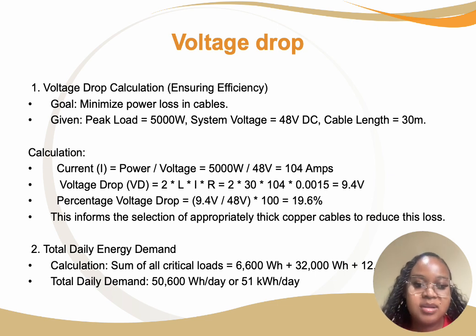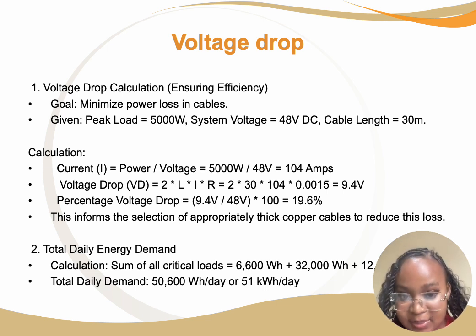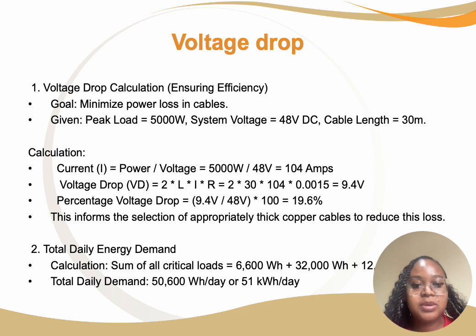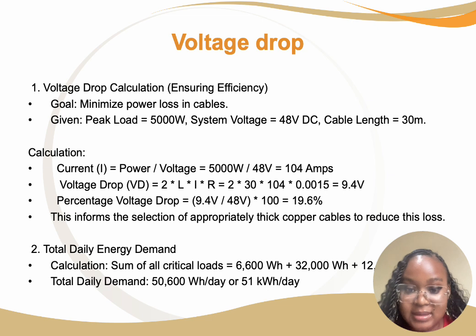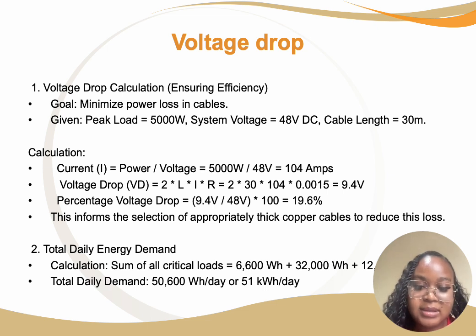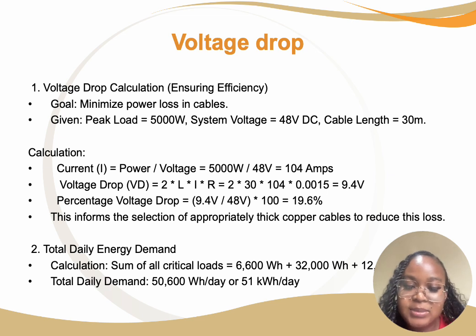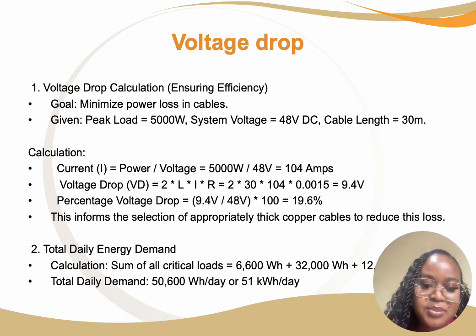Then we went and calculated our voltage drop. The goal of calculating the voltage drop is to minimize power loss in cables. We're given the peak load of 5,000 watts, the system voltage of 48 volts DC, and the cable length of 30 meters. To calculate our current, we use power divided by voltage, which is 5,000 divided by 48, and then we get 104 amps. So the current is 104 amps, then the voltage drop is 9.4 V.